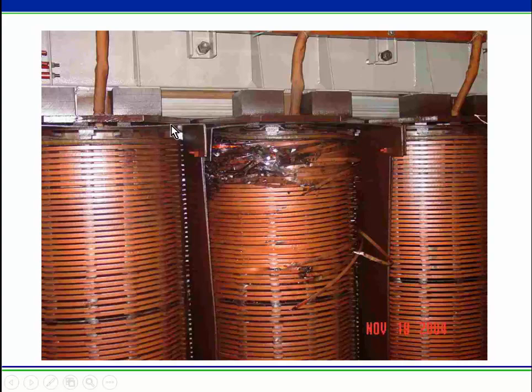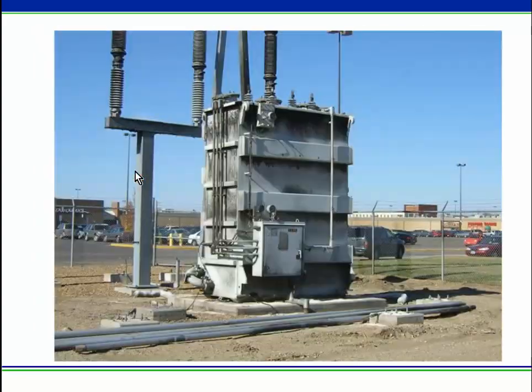Notice the steel, and the wood, though you can't see it too well. They're built very beefy. A few things go on with these. One, notice the spacing on the coils. That allows oil to circulate and keep the coils cool. And then the steel and the beefiness of these things is to deal with fault currents. When you have a lot of current flowing through these coils, there are a lot of magnetic forces associated with that. And with a lot of magnetic forces, you have torque, right? So things like to come apart sometimes.